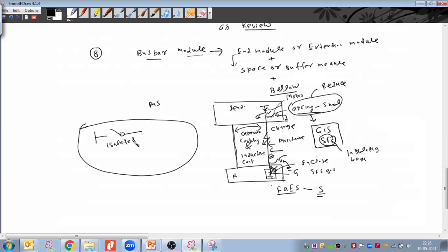And ideally the earthing switch should be closed when your isolator is open, right? In that case, if you accidentally close the earthing switch, what will happen? A short circuit will be created, a line to ground fault, no? So this earthing switch module is designed with the facility that it is capable of closing on any live circuit two times in its life, without damaging. And due to this reason, it is called a make-proof earthing switch. Okay, sir.